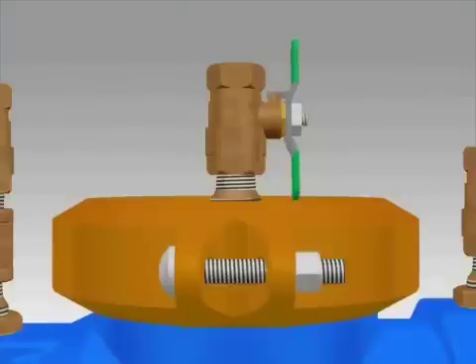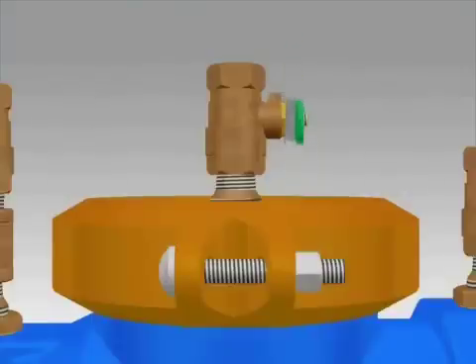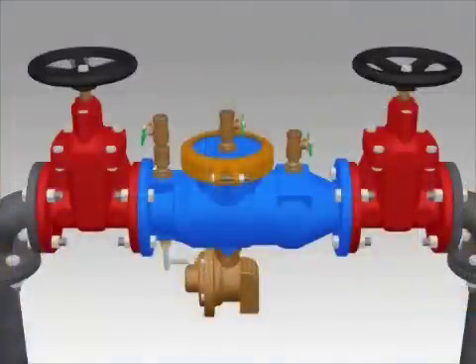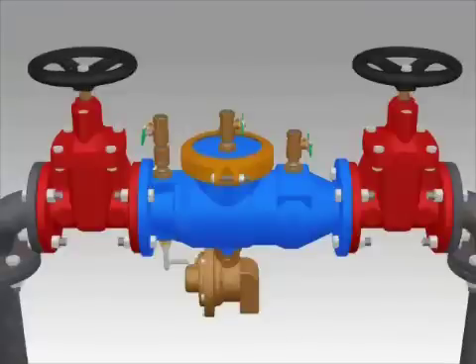Close the number three test cock. Open your inlet valve slowly to pressurize the assembly. Inspect for any leaks. Open and then close test cocks to bleed air from the assembly.